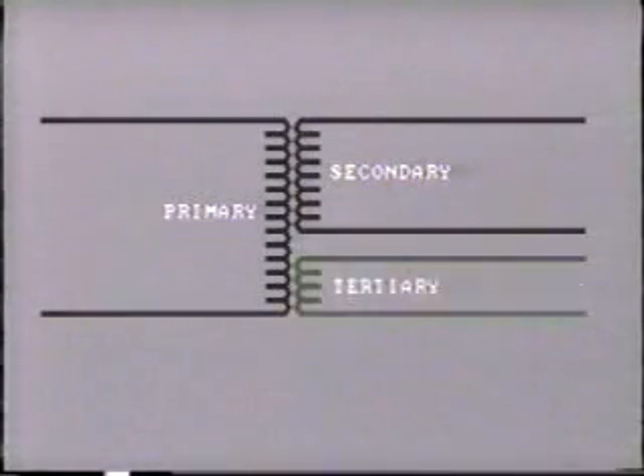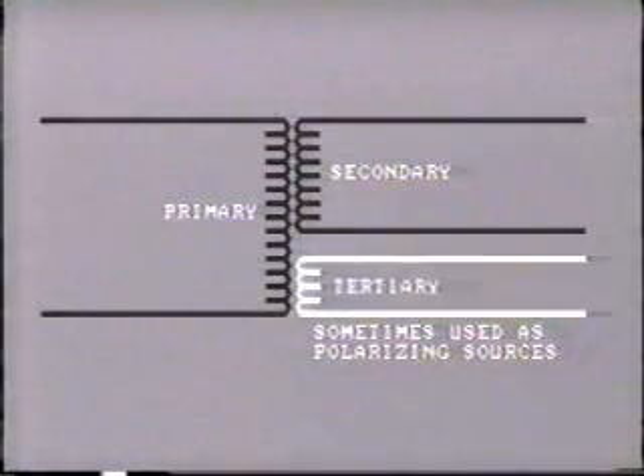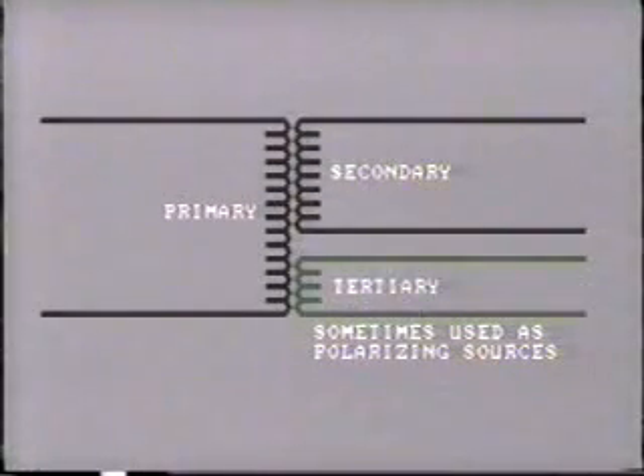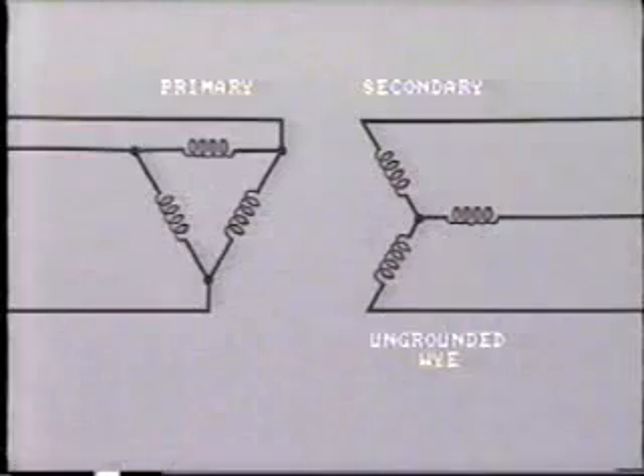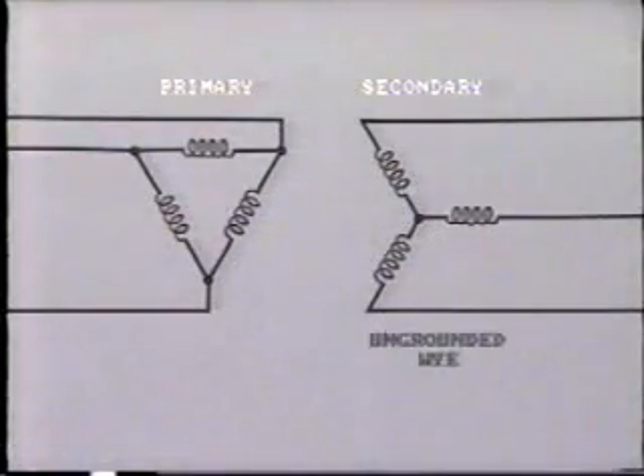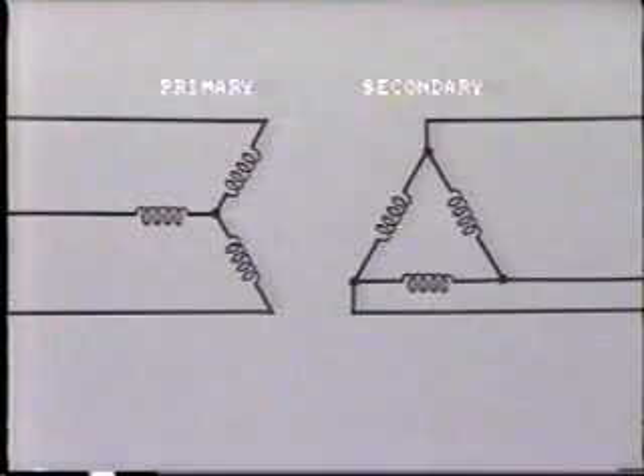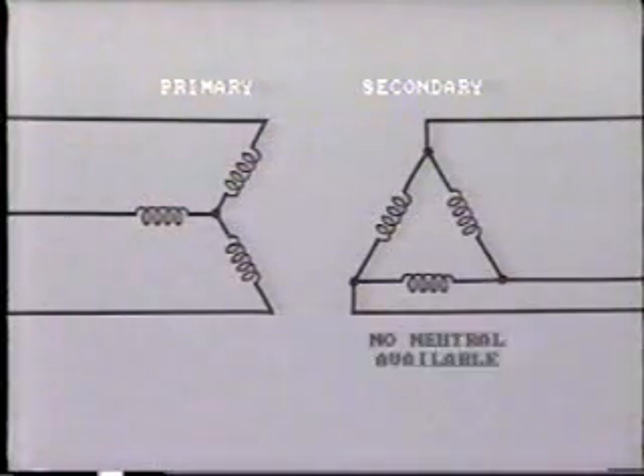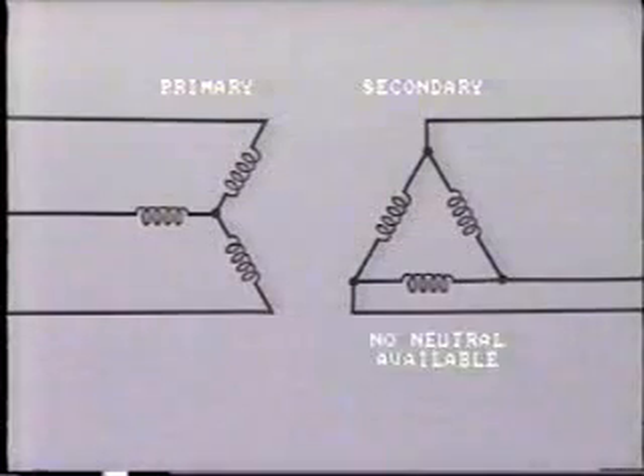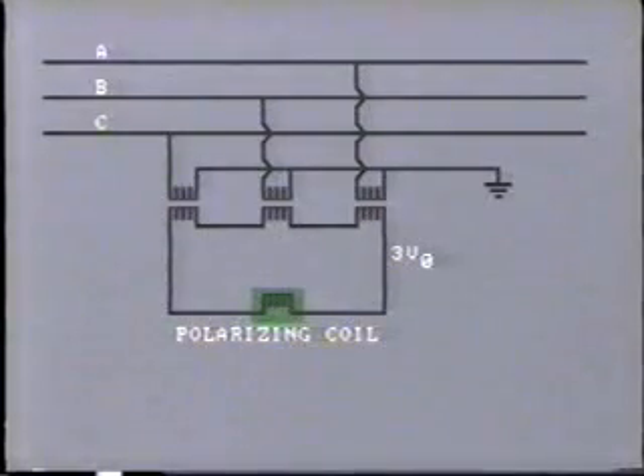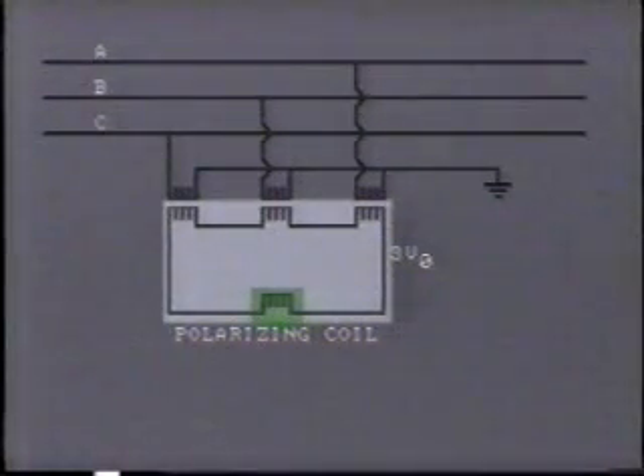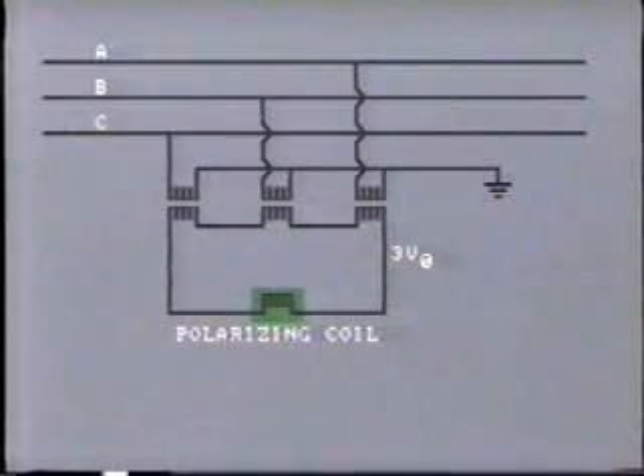Transformer tertiary windings are also used sometimes as polarizing sources. These simple methods of current polarization are not always possible. For example, the neutral of the transformer may not be grounded, or if we are dealing with the delta connected side, there is no neutral available. In these circumstances, the directional relay would be polarized by voltage, and this is usually obtained from a broken delta connection like this. We have seen this arrangement before in this program.